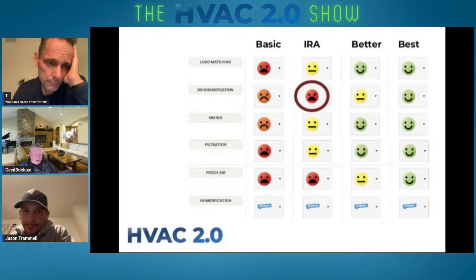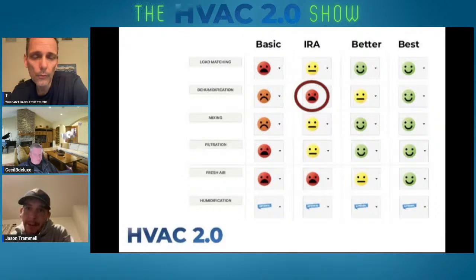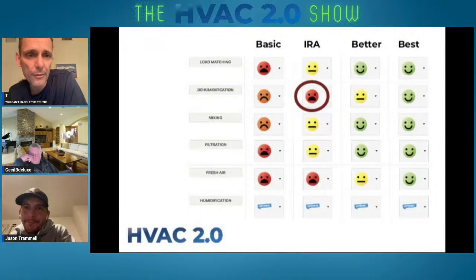So you're talking about an air handler or air conditioner? Either one. If you put a 3-ton outdoor unit on a 5-ton air handler or a 5-ton coil... If it's a 5-ton coil with a 3-ton outdoor unit, why wouldn't the airflow be the same as just a regular 3-ton? Well, it can be, but the way it's rated is at a higher airflow. So it's the same airflow across the 3-ton coil as it is across the 5-ton coil. From a perspective of airflow per surface area, it'd be less for the bigger coil. Yeah, and so it doesn't have to be as cold.